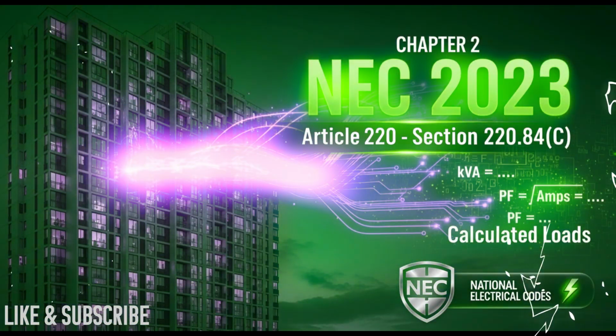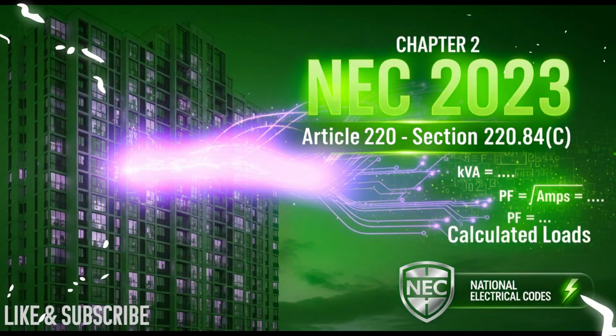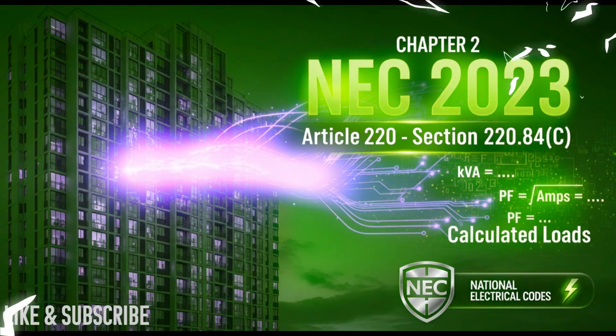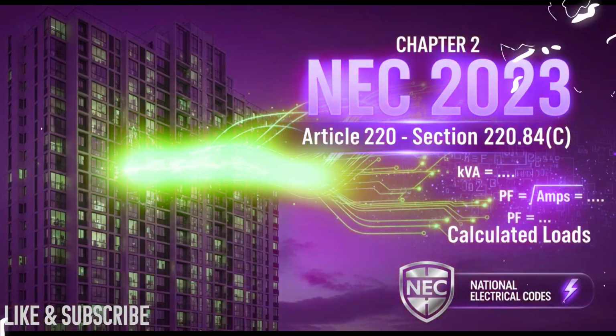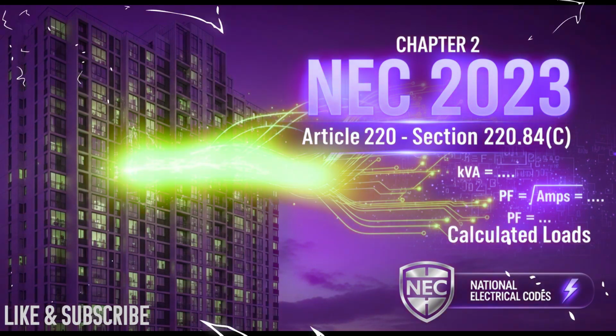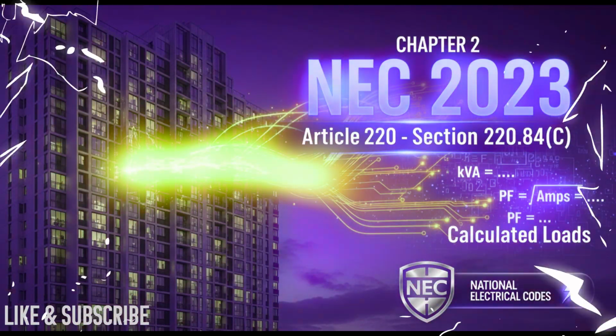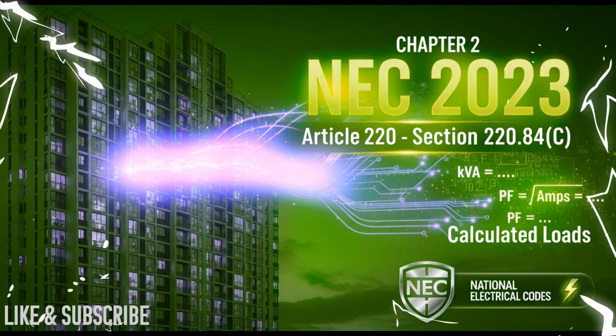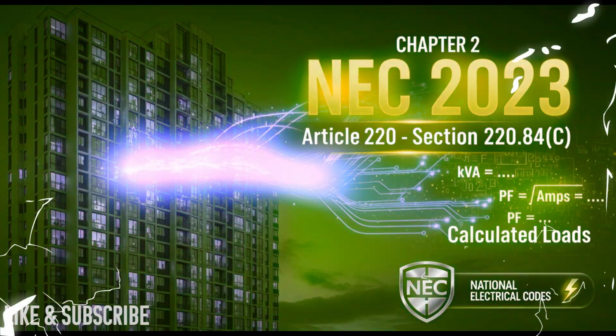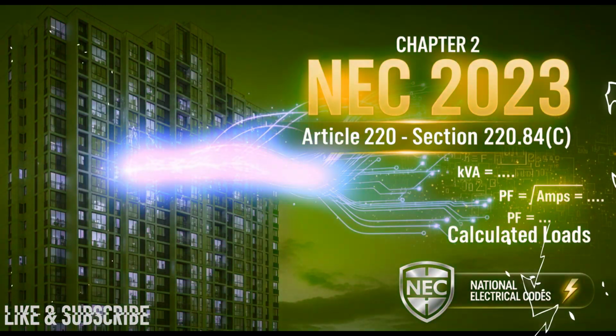Absolutely. This isn't just about avoiding tripped breakers. It's safety, it's making sure the system lasts, and honestly, it's about avoiding massive cost overruns on the main gear. Cost implications, yeah. So our mission here is to uncover those exact factors, the mandatory minimums that really shape a modern building's electrical backbone. And what's really interesting is how the code doesn't trust guesswork or estimates. It forces designers to calculate this baseline load. Think of it like a non-negotiable safety floor. So it doesn't matter if the tenant installs super efficient LEDs. Doesn't matter, or if they have some ancient power-hungry stove. The code demands capacity for, let's call it, the reasonable worst-case scenario.